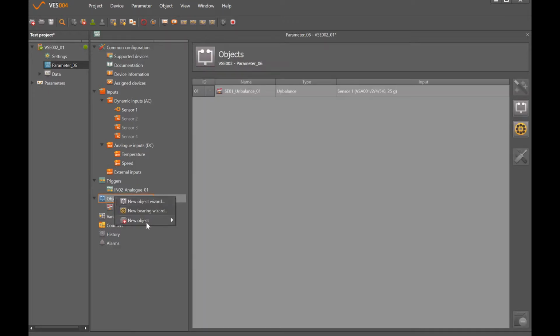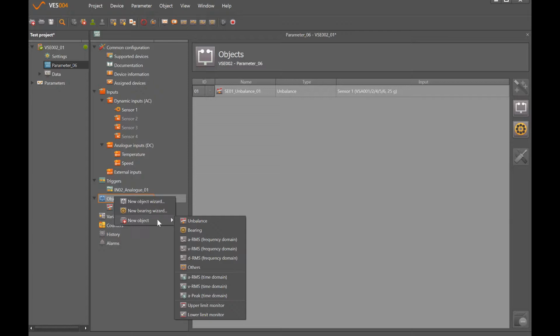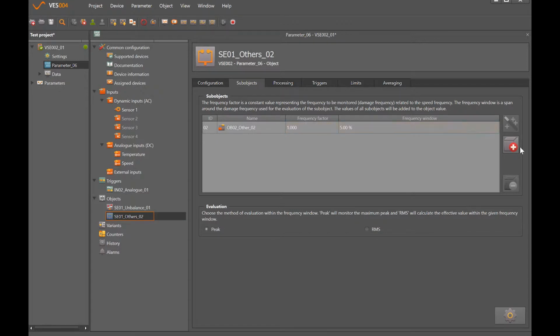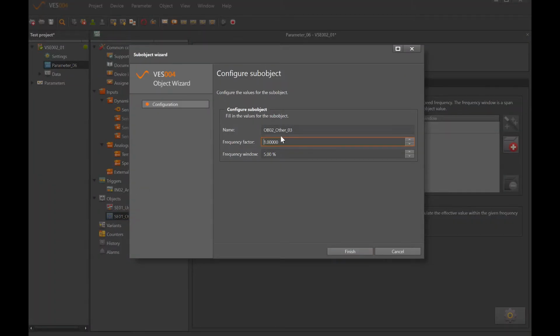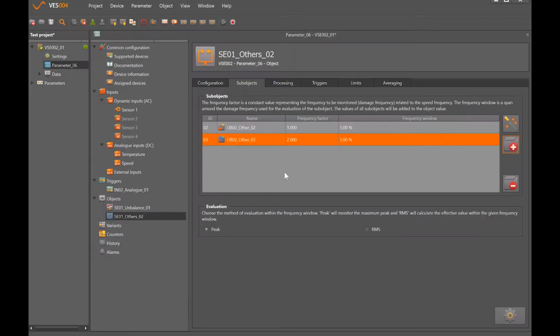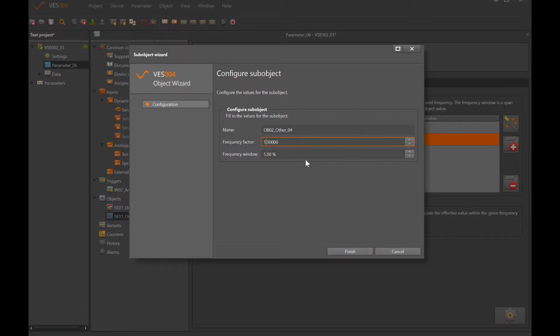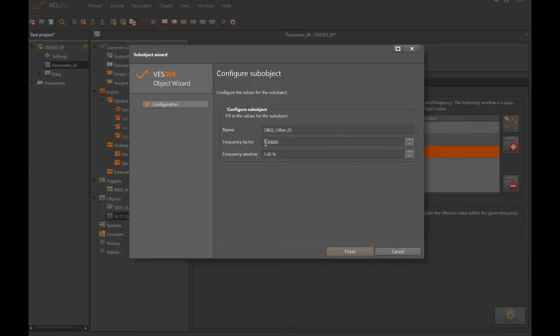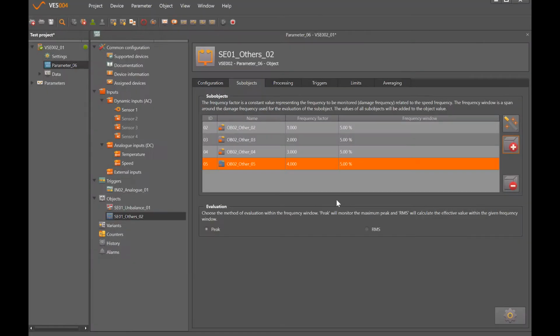The next parameter we will do is we will try and look for misalignment on the machine. So what we want to do with that is others, and that allows us to actually set fault frequencies based as multiples of the speed frequency. So if I go to sub-objects, and then click on add a new one, we can just put in 2, 3 times, and 4 times. And what I'm going to do is I'm going to remove the 1 times.